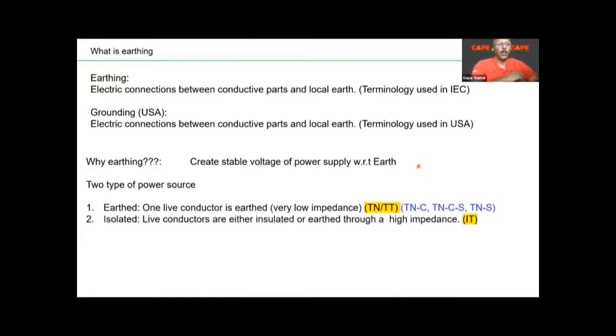Now, there are two types of power sources. One is called an earthed system. In an earthed system, one live conductor is earthed through a very low impedance. That means a direct connection: you take a wire and connect one of the lines to earth. Here the word earth doesn't mean an earth electrode in soil. It means a bus bar. So that is called an earthed system, which is generally termed a TN or a TT system. TN is subdivided into TNC, TNCS and TNS systems.